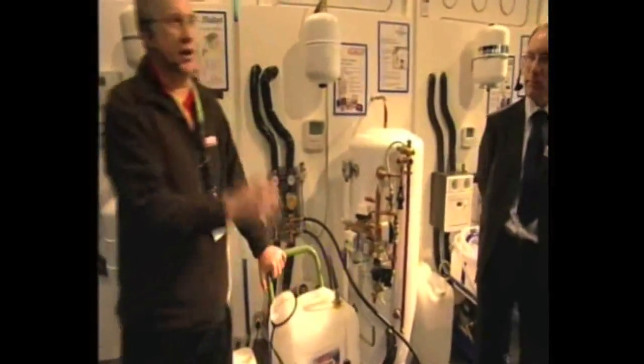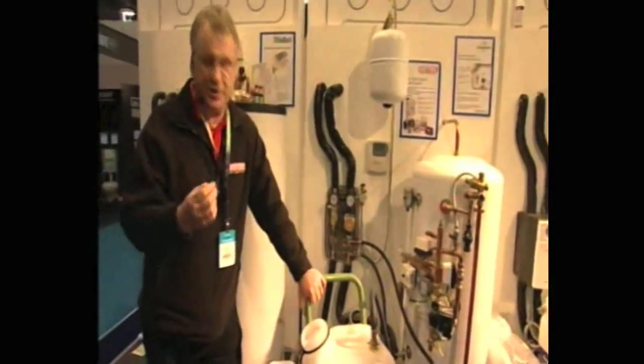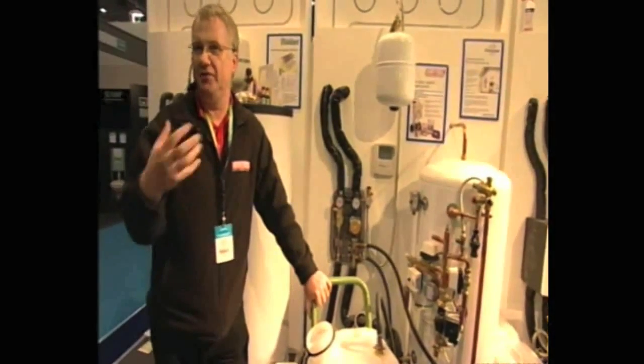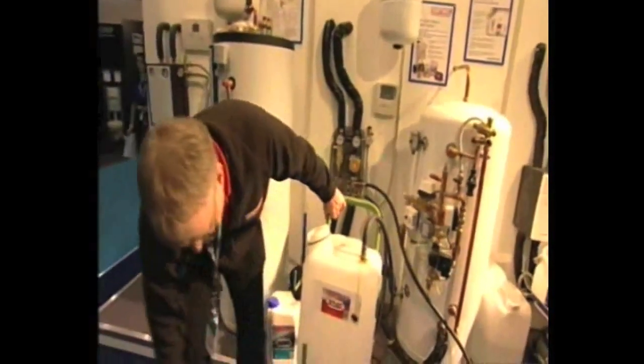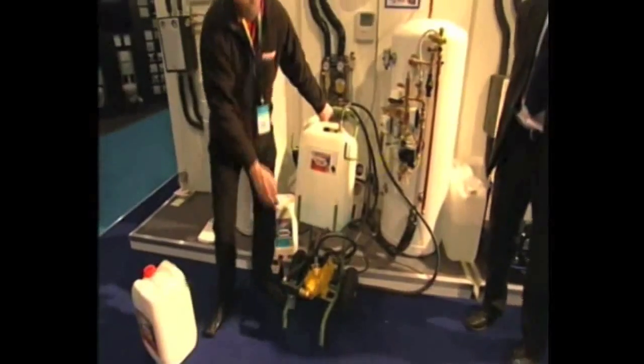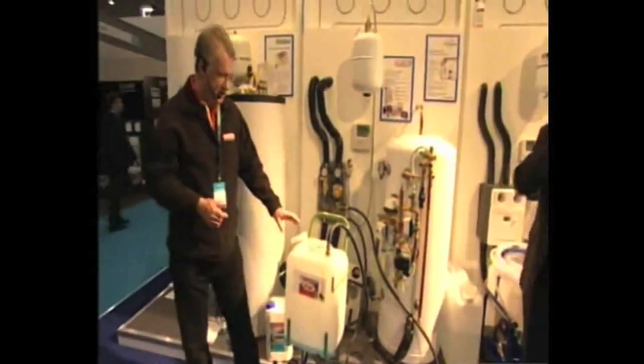So all blockages and deposits, they get removed? Right, when the pump, the first thing that's happening is the pump is taking out the air from the system, and then it's also taking out any debris that was left in there, any physical debris that was left in there from the installation. And you see on the pump at the bottom here, there's a small filter, so that will capture any physical debris. So you're going to get rid of the air and the debris from the system.